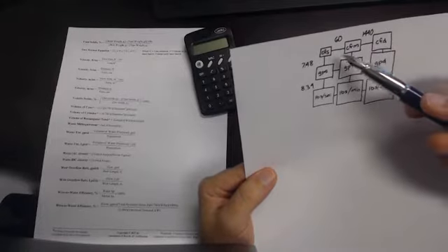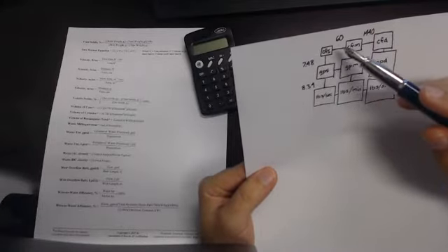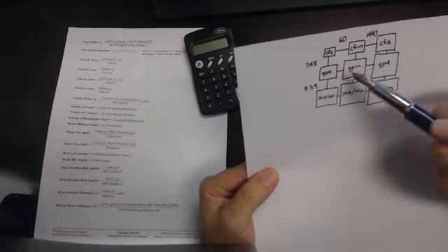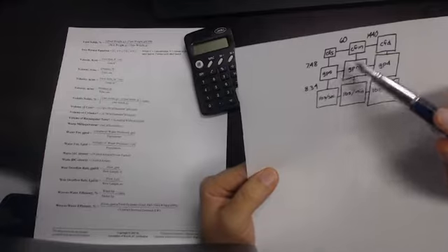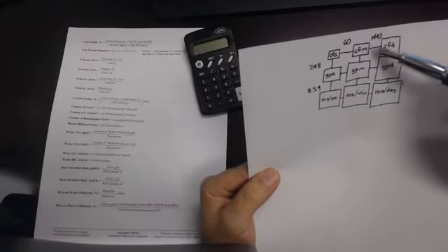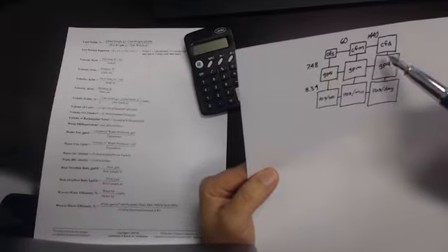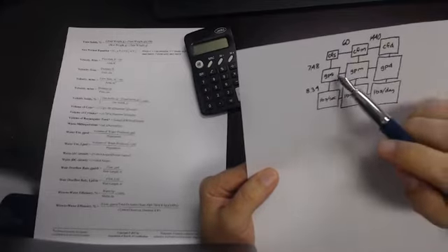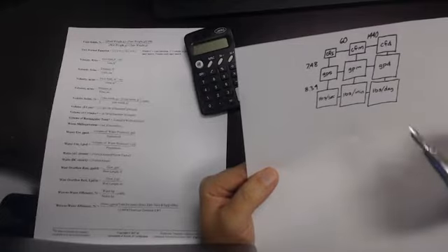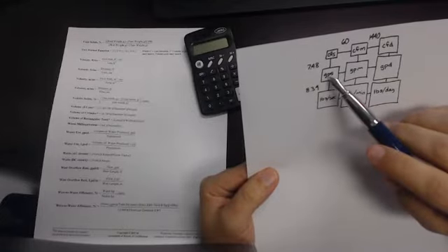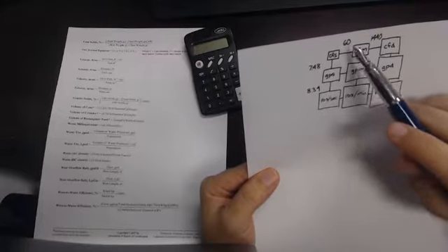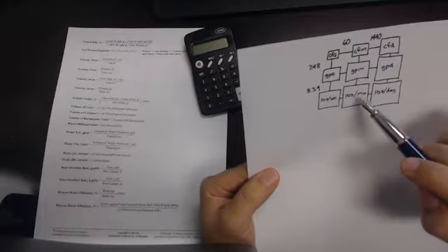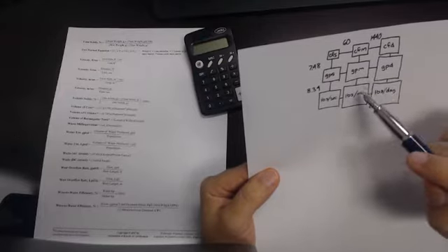So the way this works is, anytime you're going from a smaller box to a larger box, then you multiply. Anytime you're going from a larger box to a smaller box, then you divide. And all of these are 60, all these are 1440, all of these lines are 7.48, and all of these are 8.34. So say you want to go from gallons per second to pounds per minute. All you'll do is take your number in gallons per second, multiply by 60, because this is a bigger box, and then multiply by 8.34, because this is a bigger box. And that's all you'll have to do to convert it.